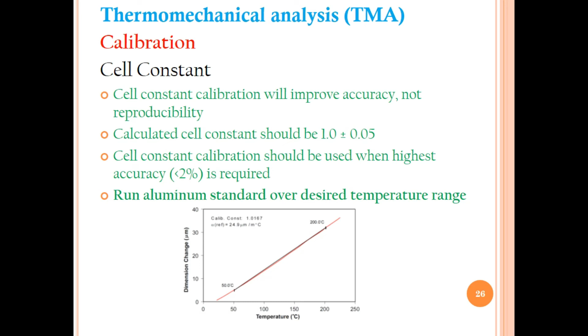Aluminium metal is used for the cell constant calibration. Run the aluminium standard over the desired temperature. In this graph you can see it is run between 0 to 250 temperature, and dimension changes in micrometers can be seen. It is run from 50 degrees to 200 degrees centigrade. The calibration constant is 1.0167, while the reference is 24.9 micrometer per meter per centigrade. So this is aluminium. Aluminium is the standard for the cell constant used in TMA instruments.